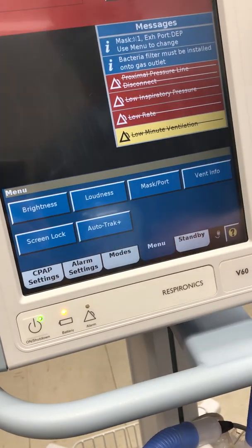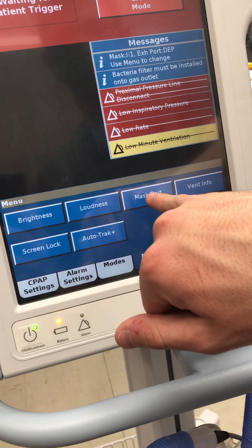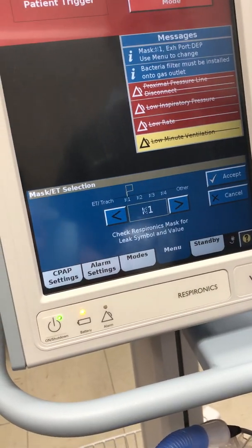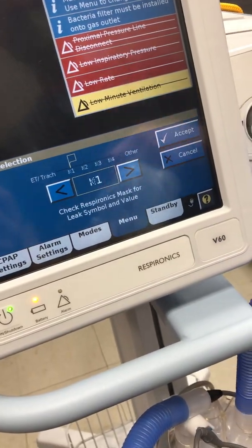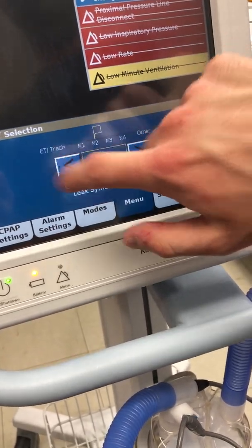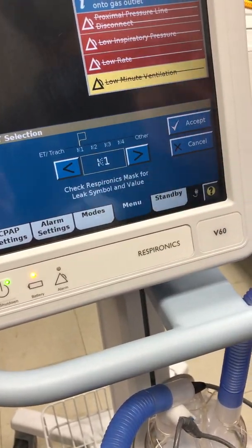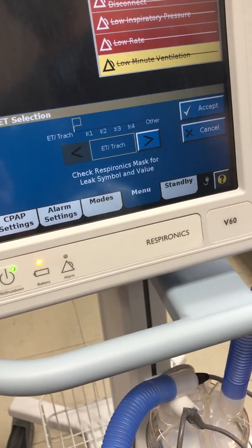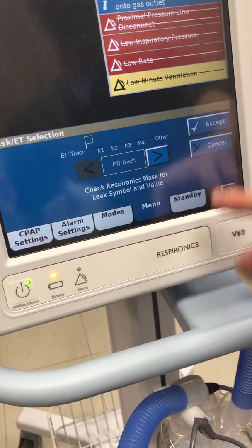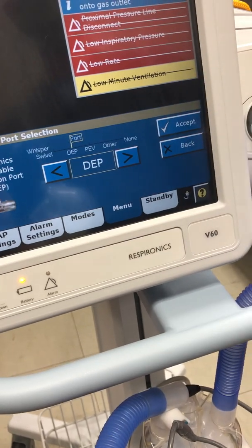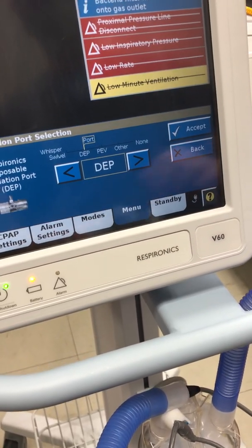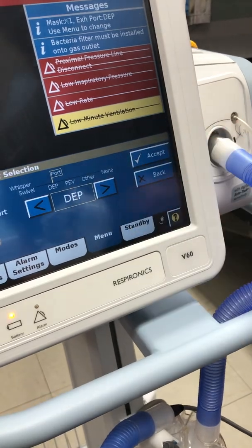For the menu, you will want to go here and you want press mask and port. So this is where the number comes into play. Number one. If the number says 2, then go to 2, 3, 4, other, specify what other means. And if they're intubated or on a trach, you want to go into intubated or trach mode, so ET or trach. So then let's say you do 1, you press accept. Next it will ask you what exhalation port you have. So this guy here, we have a disposable exhalation port, a DEP. So we choose a DEP.